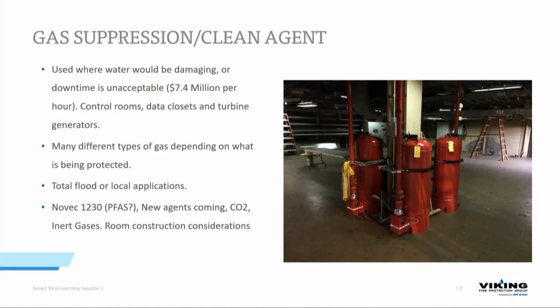And the other thing to take into consideration is whether it is a total flood application or a local application. Total flood, again, that data closet, the entire room is going to be filled with that gas. Unless you're using CO2, these gases are not going to knock you out. They're not going to cause problems for the people working there. But there are room construction considerations that need to be taken into account if you are using a total flood application. Local applications, low pressure CO2 on transformer bearings and turbine generator bearings are still a great solution. So we can still use those. Big open areas, CO2 is directly placed locally and takes care of most fires.